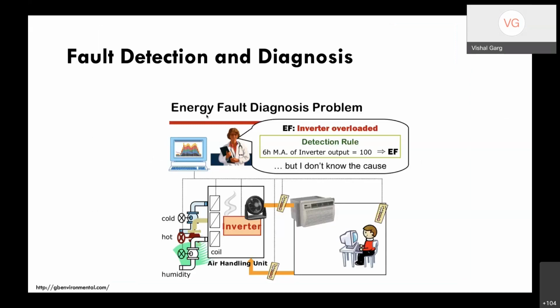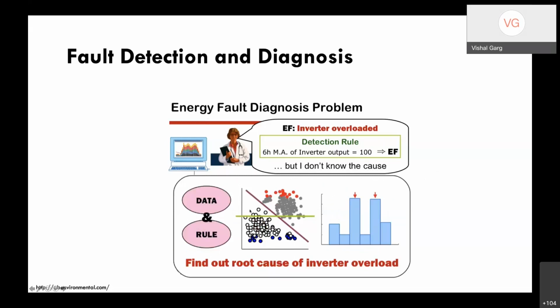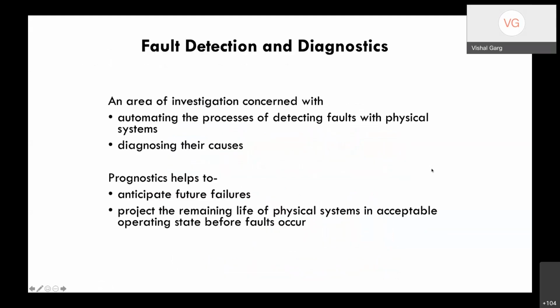It has been observed that if we carefully monitor our equipment, do preventive maintenance, and find out faults before they fail, we can save 20% of energy, and that's huge. It's just by finding the small faults and fixing them. This is called fault detection and diagnostics. It's becoming popular now, where we take a lot of data and, using this data through rules or through analytics, find out if there is a fault, if there is overload, and what is to be done so it can be fixed and energy saved. So the issue is first detecting that there is a fault and diagnosing what the fault is.